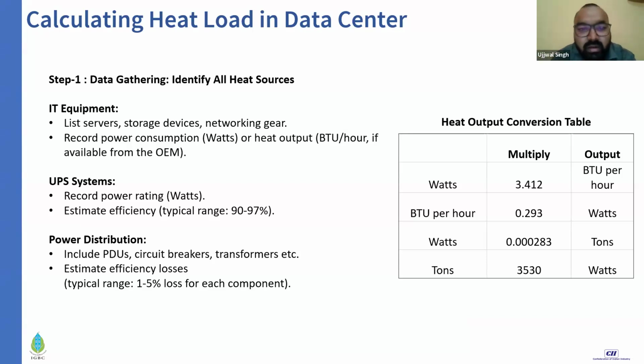Energy cannot be created nor destroyed. Whatever energy goes into a device and whatever comes out, the difference between the two is your heat generation, as simple as that. For IT equipment, there's nothing from the power perspective coming out of it, so typically whatever kilowatt consumption your IT device has is directly converted into heat.